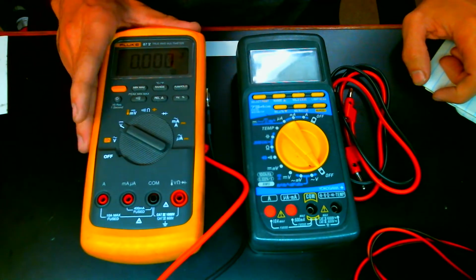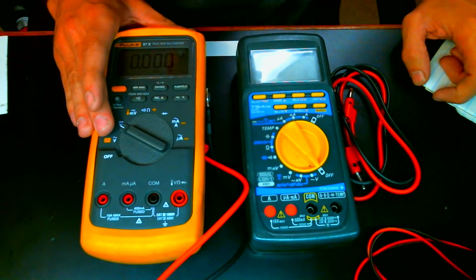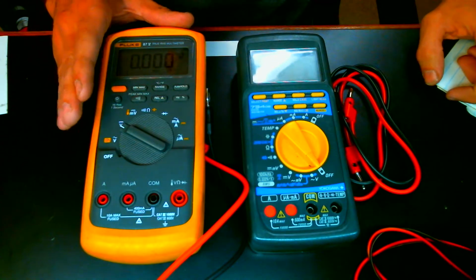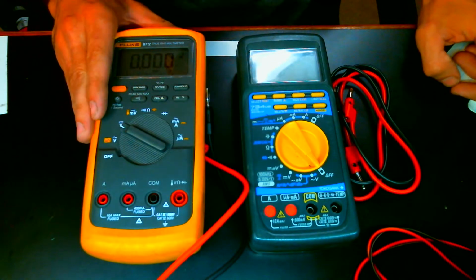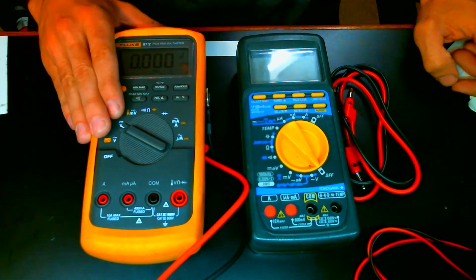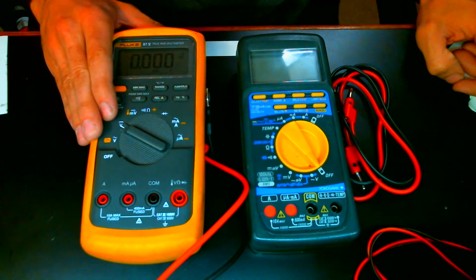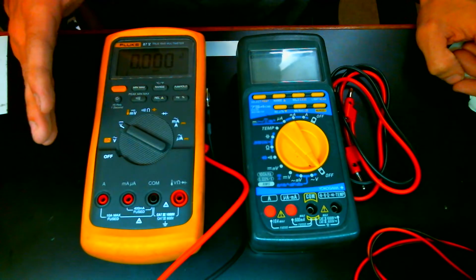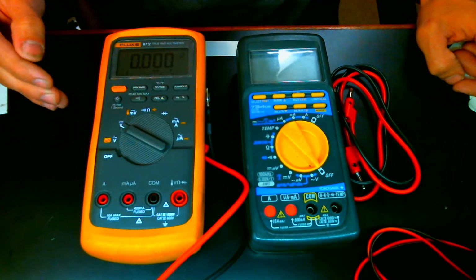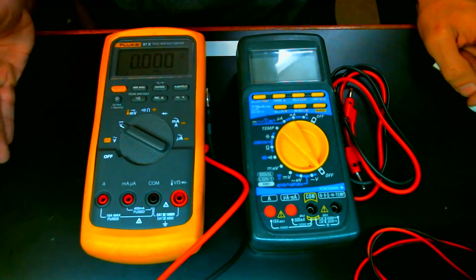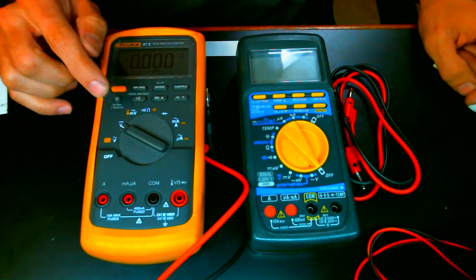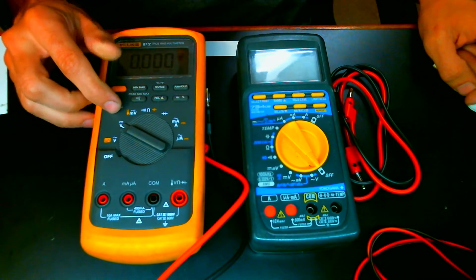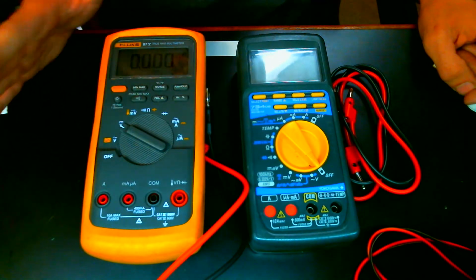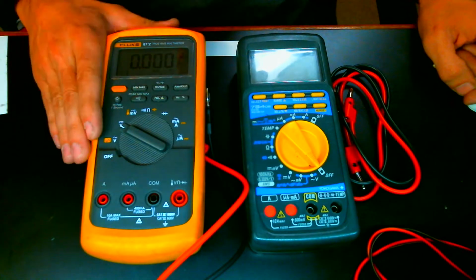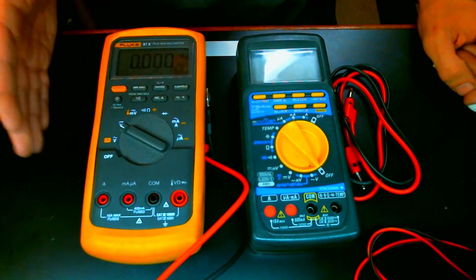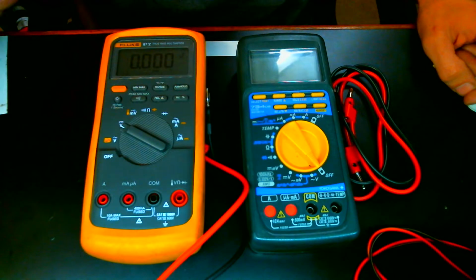This is when it gets expensive. If you're calibrating multimeters, it's very, very expensive. The equipment is expensive, and to actually get it done officially and have that traceability is very expensive. But in the end, you will get a NIST traceable certificate saying that this meter is absolutely as accurate as they say it is. But I think I've gotten a little bit off topic here. Going back to the as found, as is, as left.